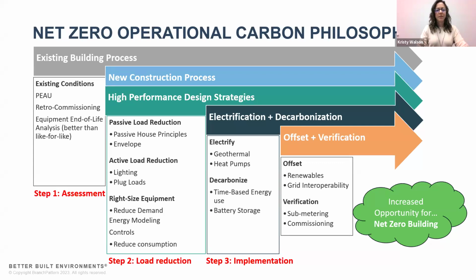The first step is really to look at your load reduction, starting with passive load reduction in the building, because the colder your climate gets, the more forward your building envelope is in the story of the heating load in the building - the more of a role your envelope plays. As conditions outside get colder and you try to maintain the same set point inside, the delta T across your building envelope gets bigger, and insulation and tightness of the building really play a huge role in reducing the heating loads.